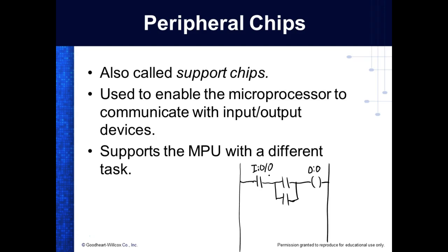So if I wanted to address an input port on this guy, I would say I:1/0, and that would give me bit 0 on this guy. If I wanted to address an input port on here, I'd say input colon 2/0. So the first number tells us the slot. The second number tells us the bit within that slot. That makes sense? Very good.